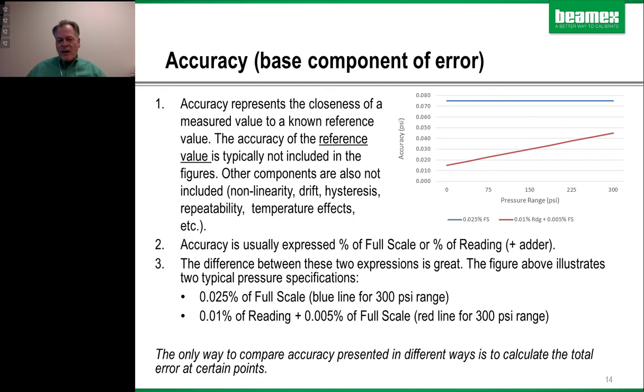Also, how do you state accuracy? Most often, and you heard me say percent a little earlier, and the 4-to-1 ratio, typically people look at a full scale value in our process world. But you may also consider a percent of reading, and then I've got plus adder here. This is sort of a base error. So if something has a percent of reading accuracy or measurement, there's usually some kind of basic base level error. And here's a little graph showing the two things. So the blue line is a 0.025% of full scale calculation for a 300 psi range. So if you take 300 times 0.025%, you get 0.075 psi.